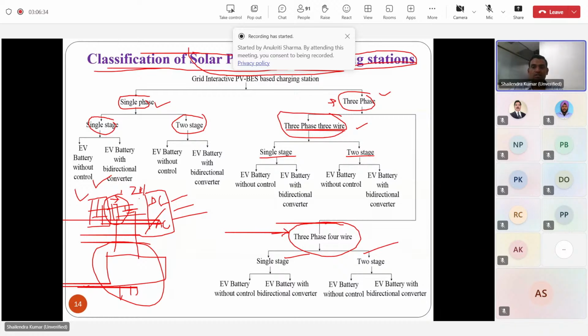Three-phase 4-wire systems are especially designed for combined single-phase and three-phase loads. These combined loads create unbalancing, and due to this unbalancing there may be huge neutral current flowing in the neutral wire, which has to be mitigated.